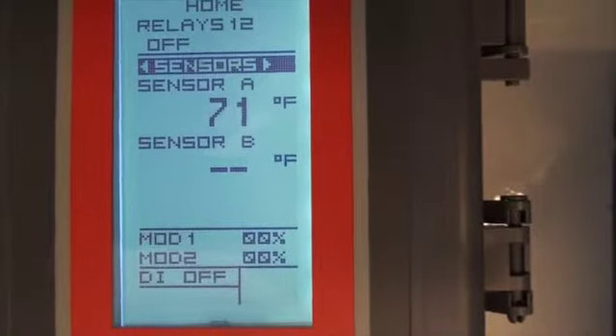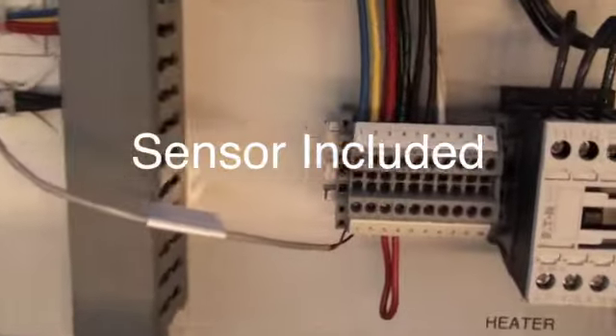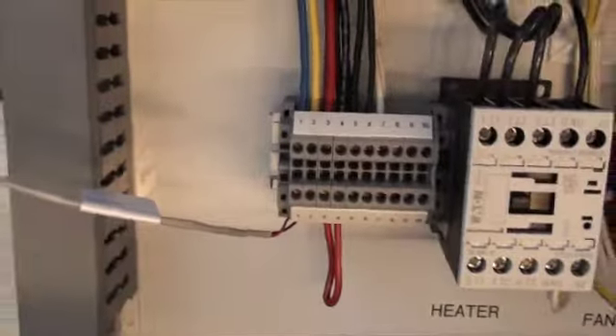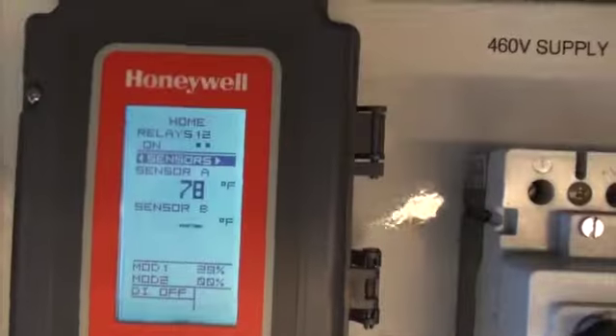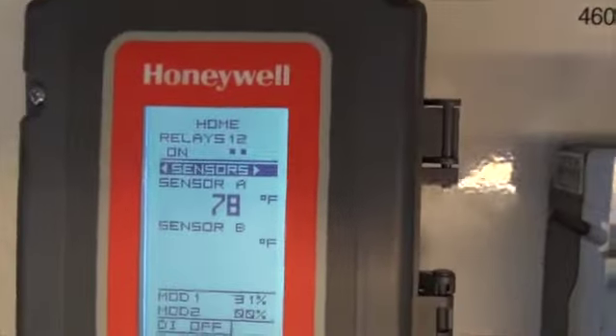It comes with a sensor, nice 2-wire type sensor. Really nice sensor because it's a 2-wire sensor, and you mount it in a well, of course. And the sensor's great because it's only a 2-wire, and there's no polarity to worry about, so you can hook it up, the red and black wire can go to the terminals either way. It really makes no difference, which is kind of nice with sensors. Don't have to worry about polarity.